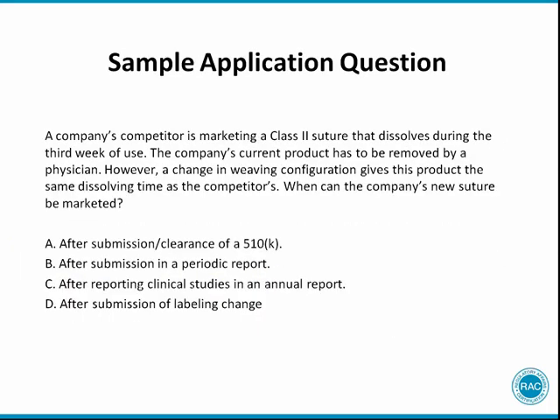This question relates to U.S. regulations. In reading the question, you first note that it focuses on a Class II medical device. The next key fact is that a competitor has a product on the market with certain additional features — the suture dissolves — and your company can make a change so that it, too, dissolves. If you know the medical device regulations, you will know this is a new intended use and thus, for this product, you will need to submit a 510-K, answer A. B and C are not correct, as periodic and annual reports do not apply to Class II devices. D is incorrect because this is not just a labeling change.